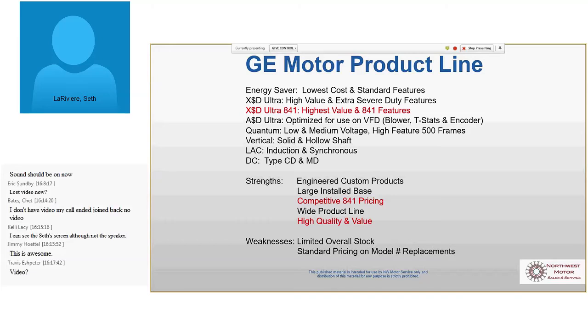They have space heaters, RTDs in the windings and bearings, so you can tell how hot your motor is getting in the windings and the bearings. Just full features and high efficiency. Then also verticals, large AC, those are thousands of horsepower, and then DC. So GE makes a pretty full line of motors.